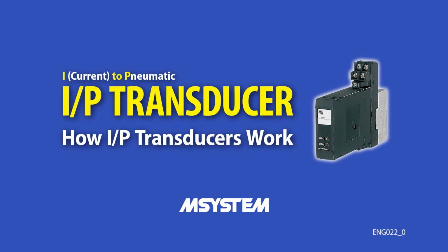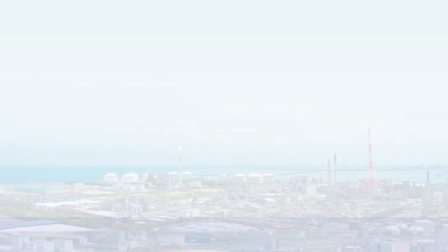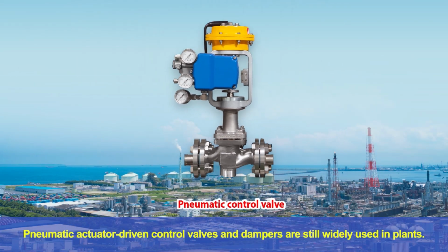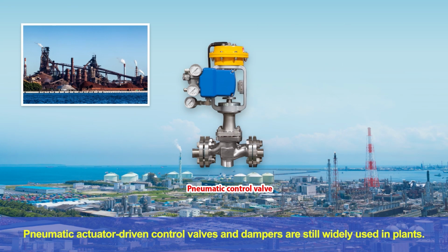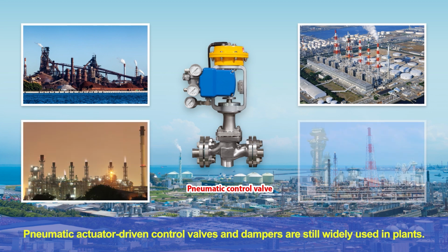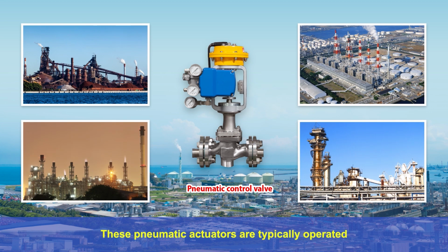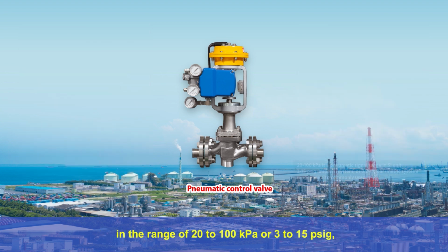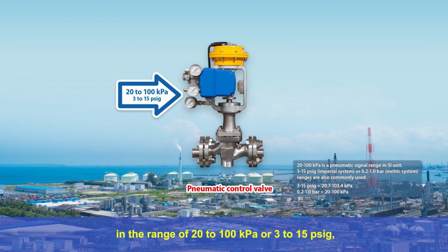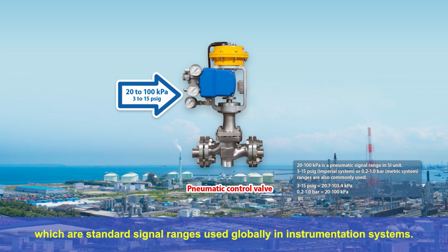This video showcases the workings of a compact, highly reliable I-to-P transducer provided by M-System. Pneumatic actuator-driven control valves and dampers are still widely used in plants. These pneumatic actuators are typically operated in the range of 20 to 100 kilopascals or 3 to 15 psig, which are standard signal ranges used globally in instrumentation systems.